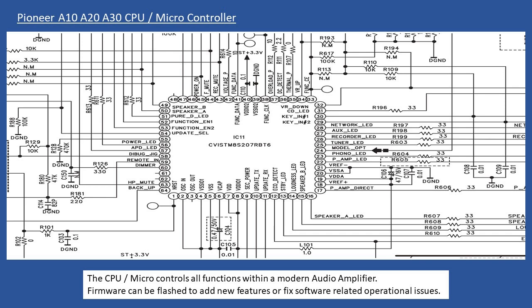Now with microcontrollers, the manufacturers or authorized service agents can, if they wish, download or burn brand new firmware into the microcontroller. And typically firmware happens for two reasons. The first one is the manufacturer wants to add some new features and functions, or they may be aware from service information coming from the field that there's an issue with the amplifier in terms of its operation. There's something not quite right, and often we refer to that as a software bug. So they will make available new firmware which can be downloaded into the microcontroller, and often on these circuit boards, it's normally underneath the amplifier via a blanking plate. You'll see a multi-pin connector where they can connect directly a PC, running the new firmware and a loader application, and it will load directly into the microcontroller.